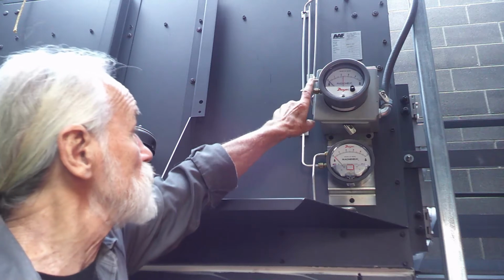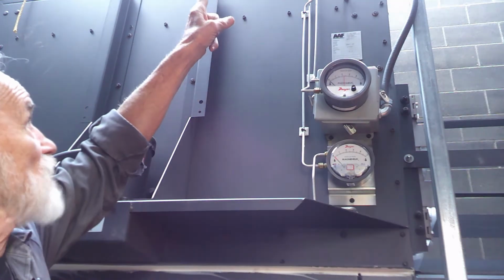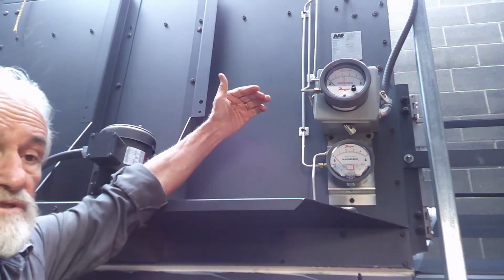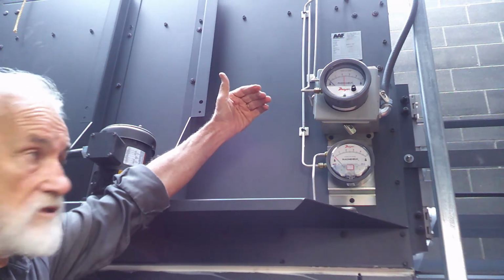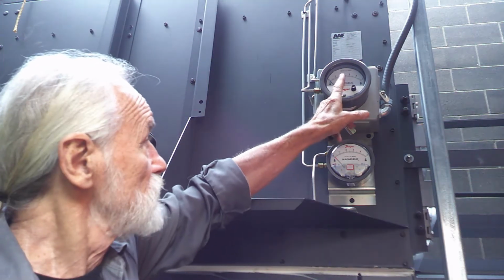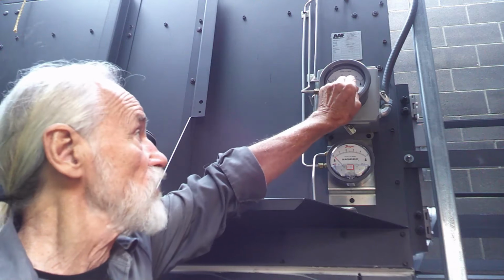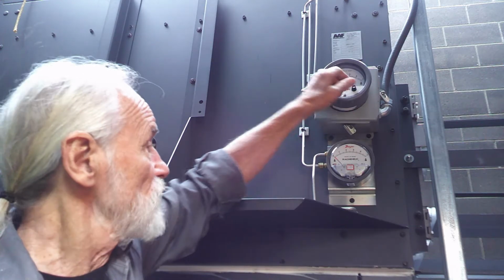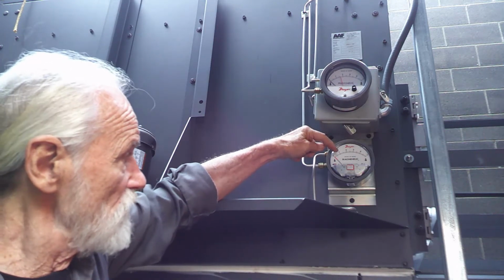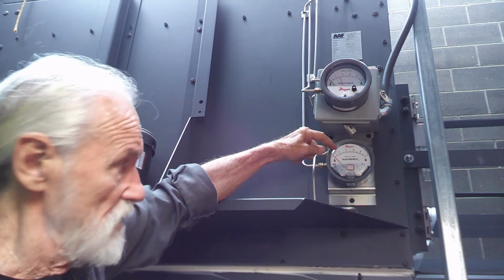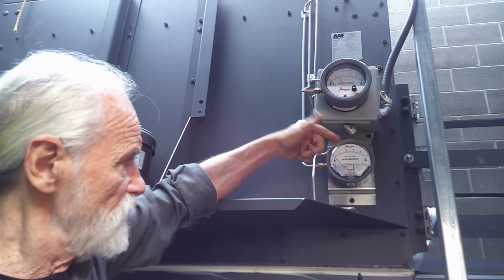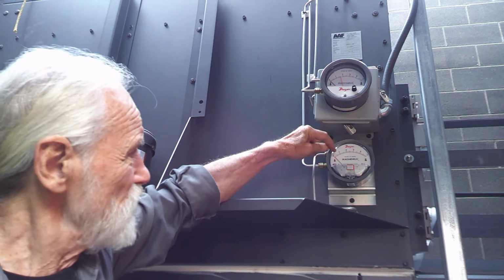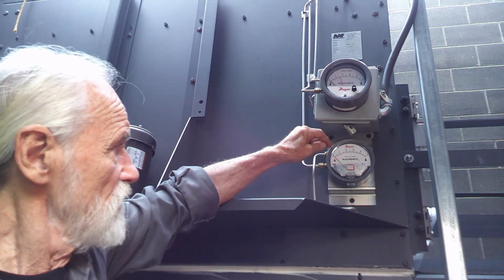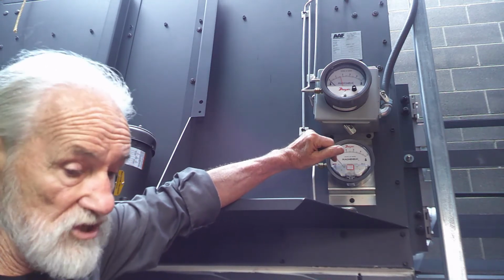You can see the tubes go up, one's high, one's low, on both sides of those filters—they're the secondary filters. When it senses something significant, it doesn't make a whole lot of difference where this is. When we run it, it'll probably read less than 1, maybe 0.5 or 0.6, because they're clean now. Anything more than about 1 or 1.5 means there's something wrong.